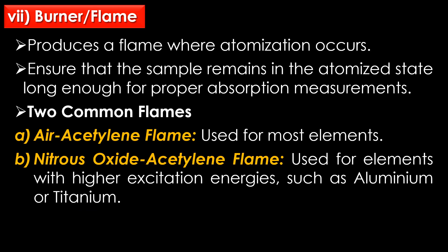The seventh part is the burner or flame. The burner produces a flame where atomization occurs, and it helps ensure that the sample remains in the atomized state long enough for proper absorption measurements. There are two types of common flames: the air-acetylene flame, used for most elements, and the nitrous oxide-acetylene flame, used for elements with higher excitation energies such as aluminium or titanium.